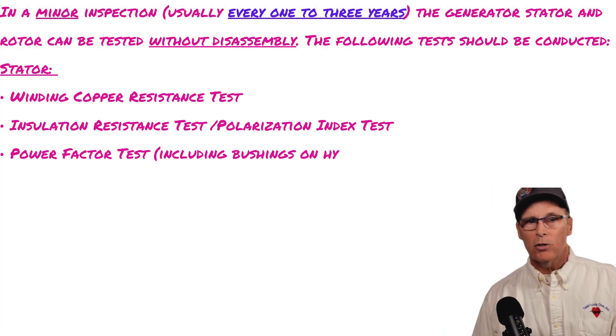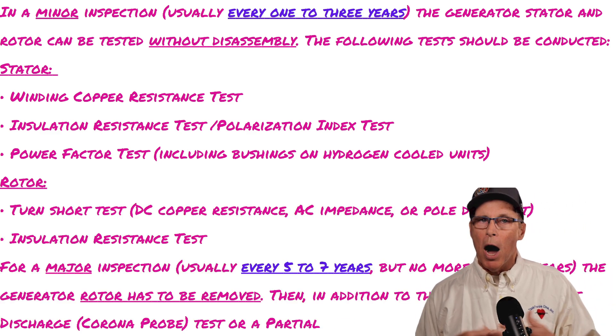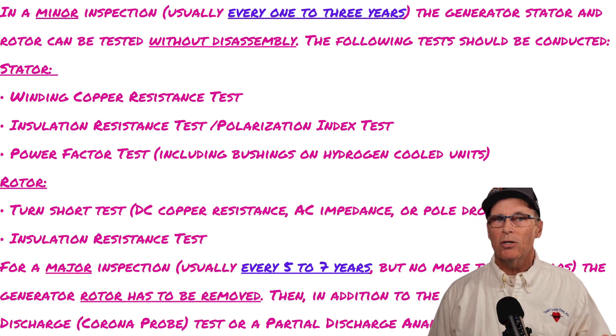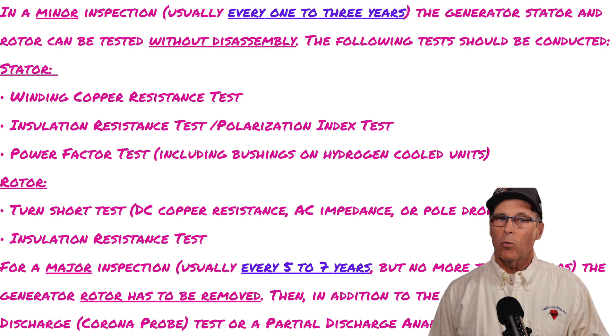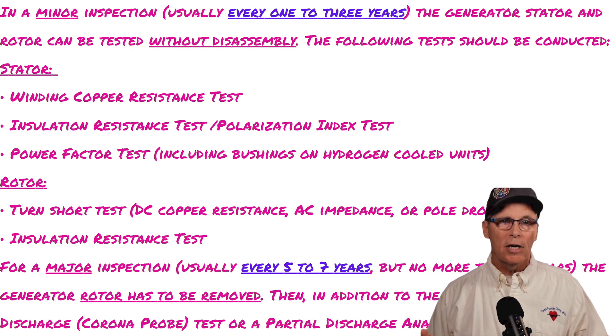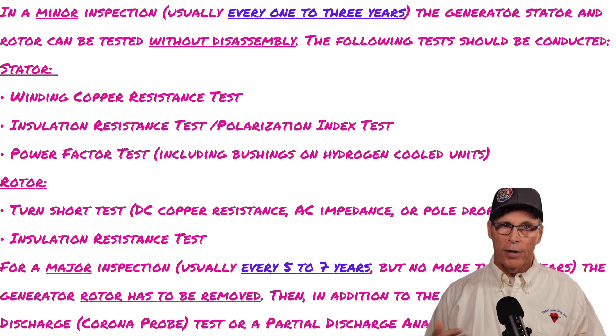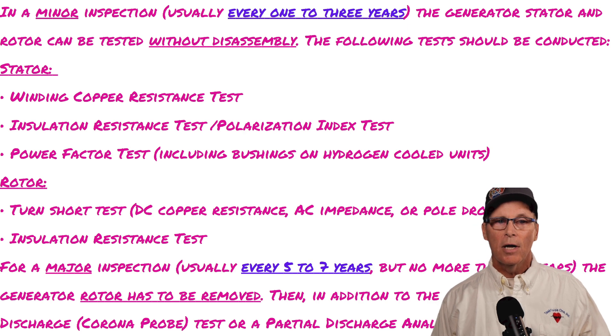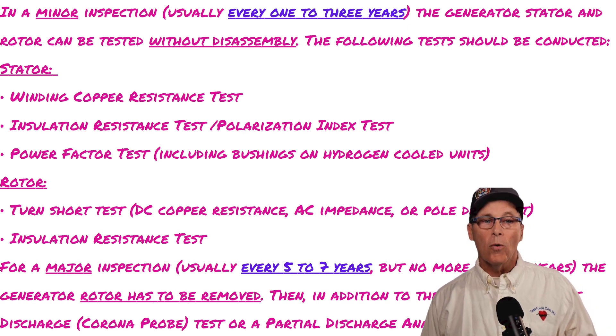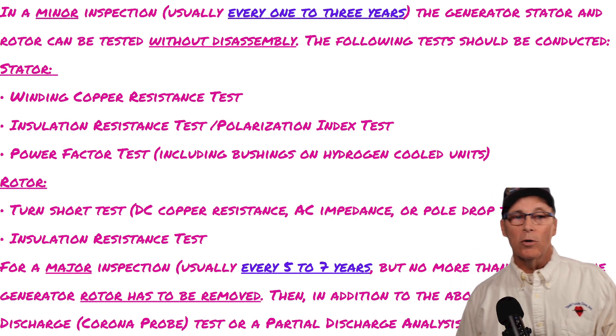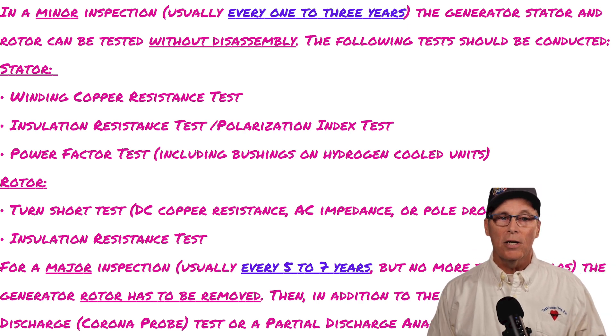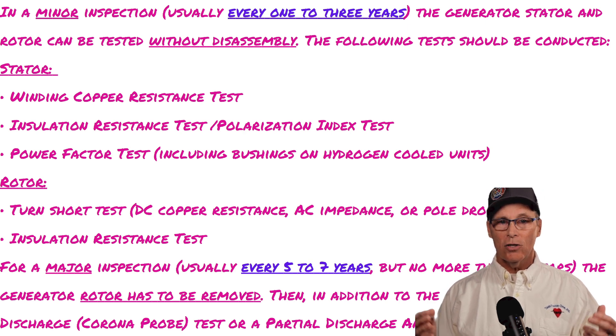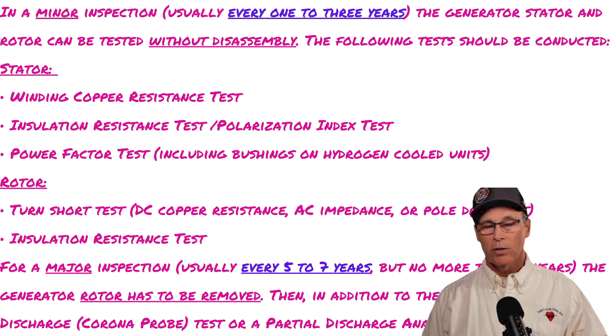For a minor inspection, typically once every one to three years, you don't have to disassemble the machine, but you'll do a winding resistance test, insulation resistance test, and power factor test for the stator. For the rotor, you'll do the turn short test and the insulation resistance test. That covers the minor inspection every one to three years.